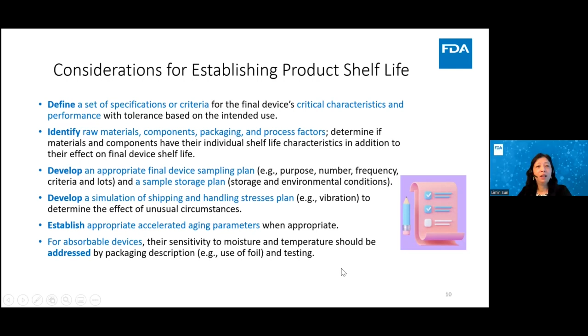Develop a simulation of shipping and handling stress plan to determine the effect of unusual circumstances. Also establish appropriate accelerated aging parameters when appropriate. For some devices that are absorbable, their sensitivity to moisture and temperature should be addressed by packaging description and testing. Here are some general recommendations for product shelf life testing. This testing should evaluate all critical characteristics and performance of aged device samples to ensure they are within the established specifications or criteria. So again, these critical characteristics and performance are device specific, which will be further discussed using a sample or examples.